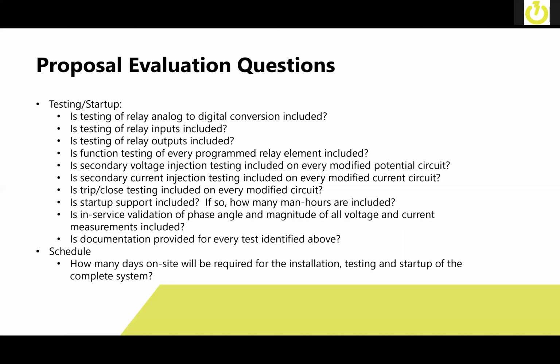Is documentation provided for all the tests identified above? A lot of times we get into a customer's facility and they may have no documentation, which means you're starting from scratch trying to figure out what may have misoperated or failed to operate throughout the system. From a schedule standpoint, how many days on site will be required for the installation, testing, and startup of the complete system? I know a lot of times people are juggling outage schedules and trying to figure out, do we need to take a 1 week outage or a 1 day outage? So that can come in handy during the proposal evaluations.